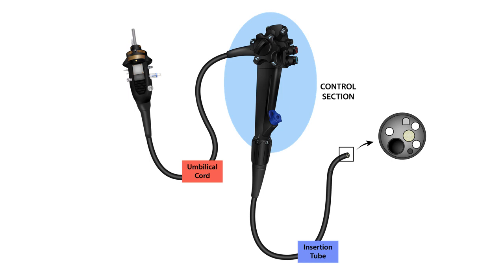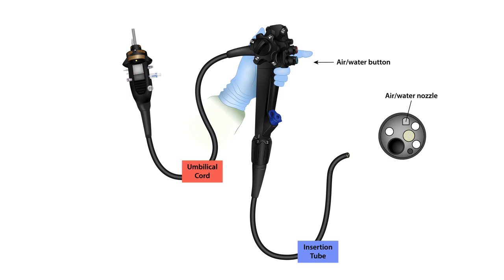So let's look at the control section. It is quite complex. It has an air-water button, and if you gently occlude the air-water blue button, air comes out. Or in routine practice, we use CO2, and CO2 comes out through this channel. If you press it further down, water comes out of that air-water nozzle, and it is a small amount of water that can be used to clear the lens if it gets dirty.